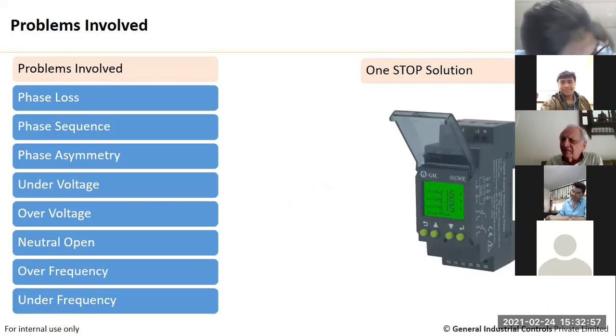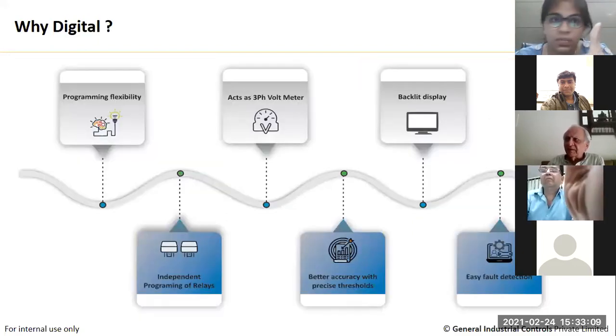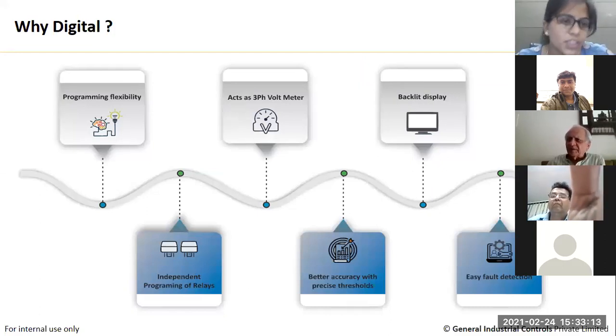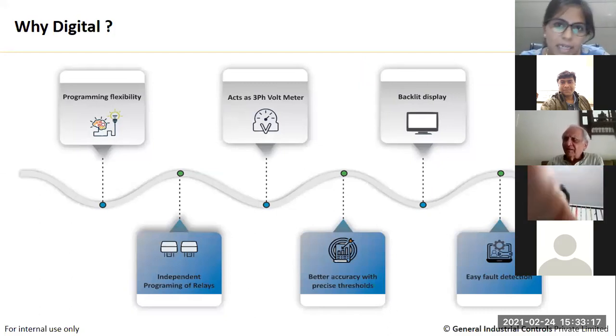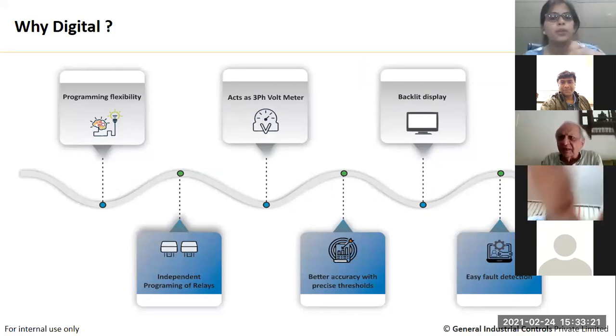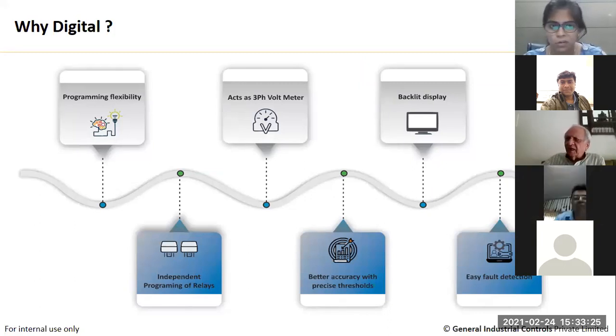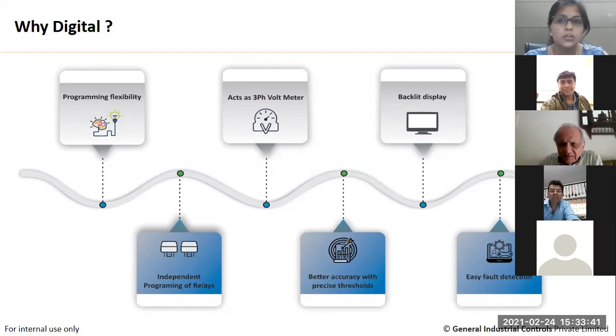Now, we have all used and seen traditional analog pot-setting relays, so why digital? Why do we need this to be digital? The first and foremost feature is programming flexibility. We have two independent relays which can be programmed independently. Suppose we want to set the first relay for over voltage at 485 volts, we can exactly set this as 485 and it will trip at that value. So it's very easy for programming, and we don't need a screwdriver for pot setting anymore.